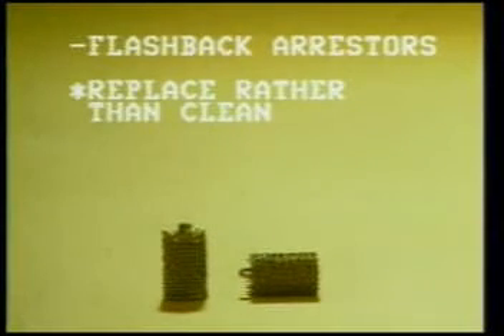If this fails to restore the flow, try the flow regulating orifice in the aspirator bulb coupling. Remove the rubber tubing connection to the bulb, then unscrew the orifice. If it is clogged, clean it by pushing a fine wire through the opening. The final flow system components that may occasionally become clogged are the flashback arresters. Because they are important and relatively inexpensive, the arrestor should be replaced, not cleaned.